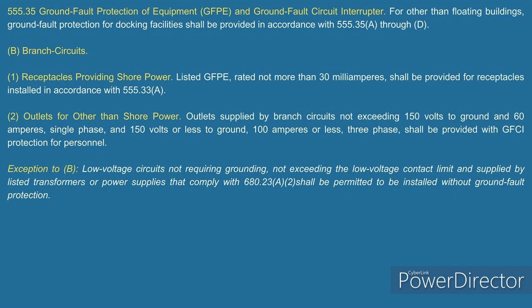If you look at B1, it talks about receptacles providing shore power. Now, he already made the statement, I've got a receptacle that's out there. He's saying you're cord and plug connecting something. That's an outlet, therefore I need to provide Class A protection. Basically, everything is considered an outlet. It shouldn't matter what this says right here because he says it's an outlet anyway, no matter what. Well, right here, they're telling you receptacles. That means I'm going to be cord and plug connecting something. Is that correct? Yes, sir.